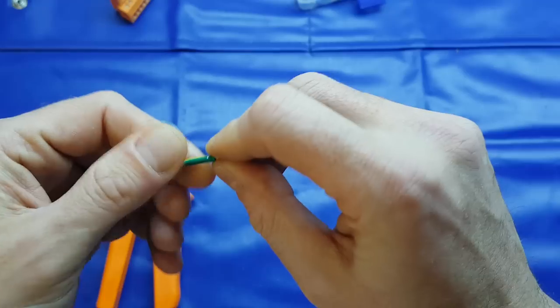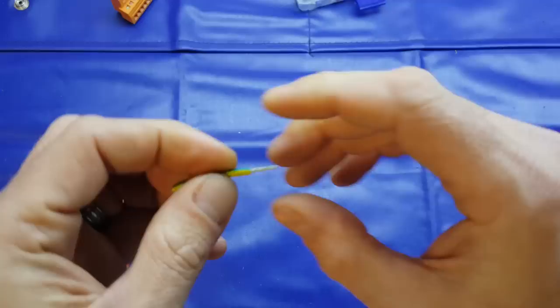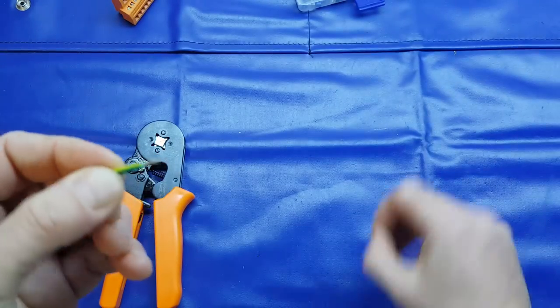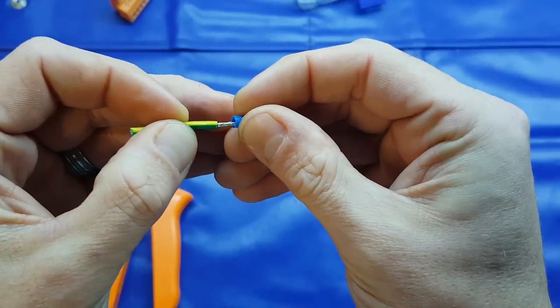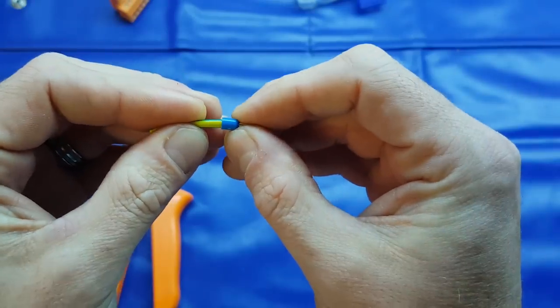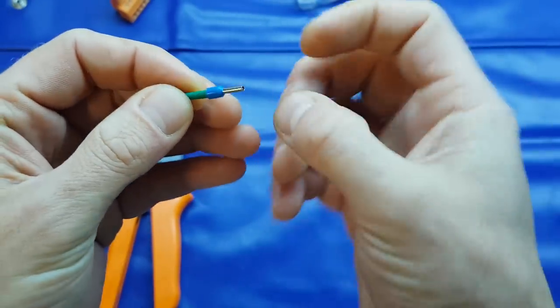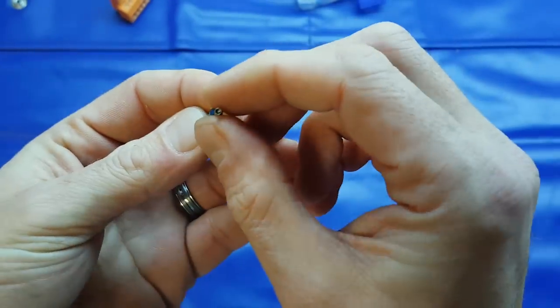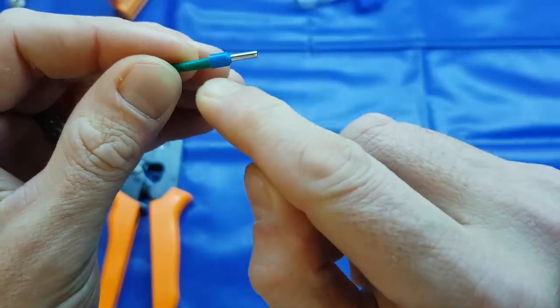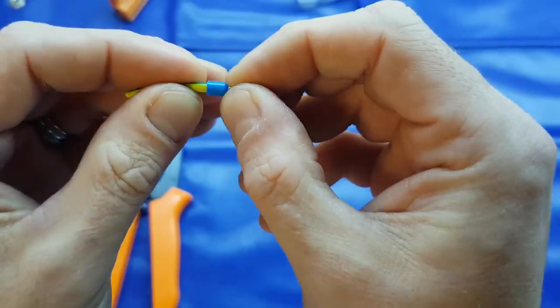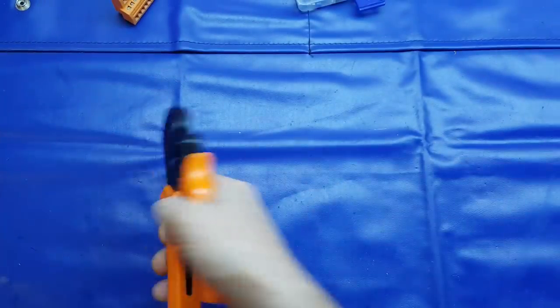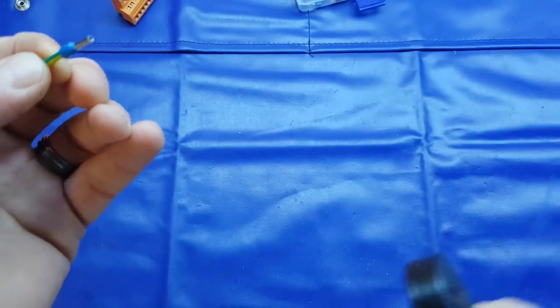But what a ferrule does is basically it stops that from occurring. You take your conductor, your piece of wire, and you place the ferrule onto the end. What that does is it basically encapsulates - if you want to use that as a word - but basically keeps all the conductors inside that metal tube and offers a little bit of insulation just to cover the actual PVC or whatever that's actually on the conductors. We then take your tool like so...